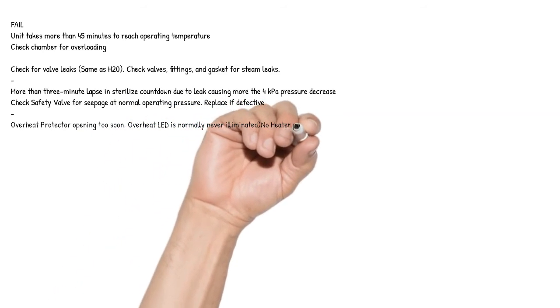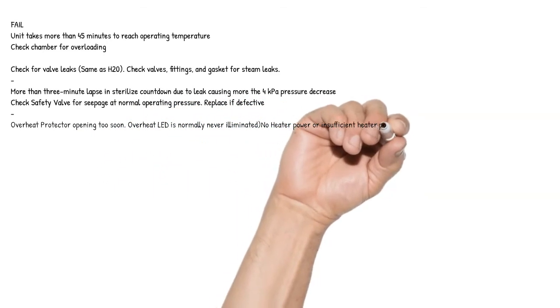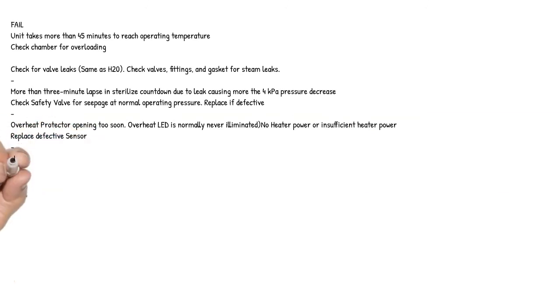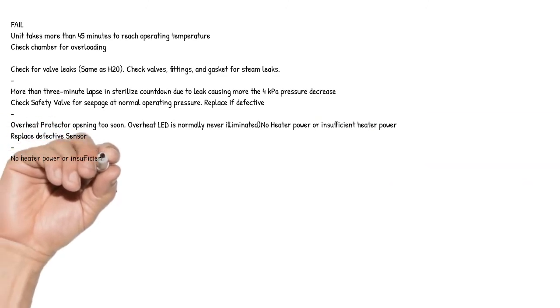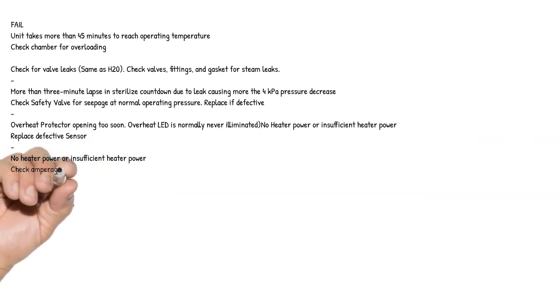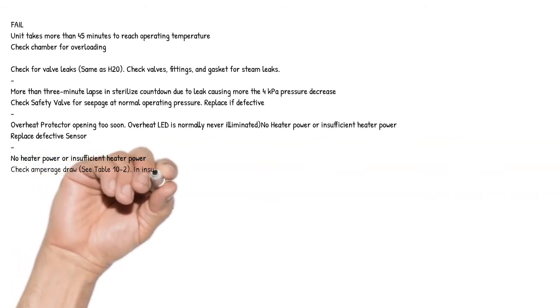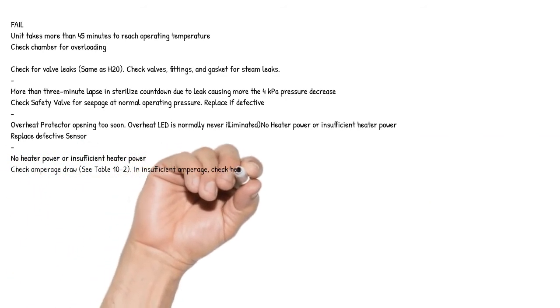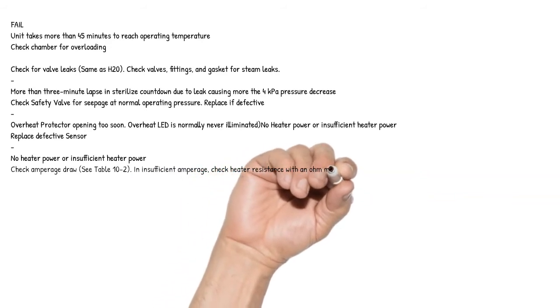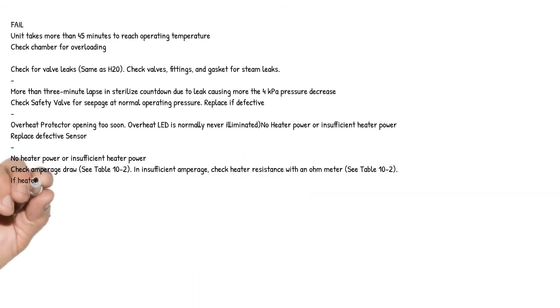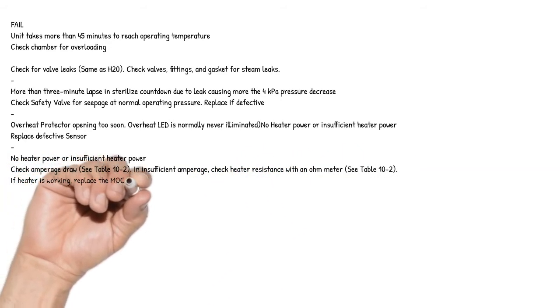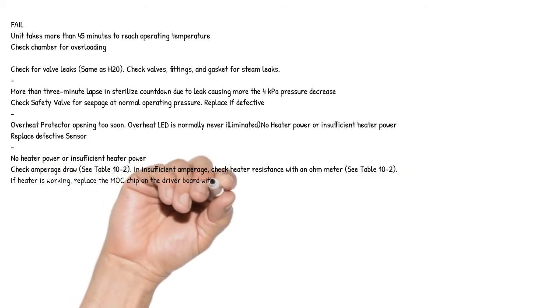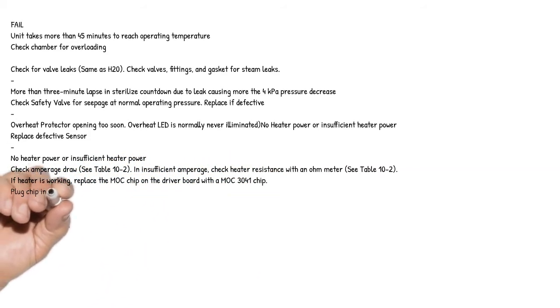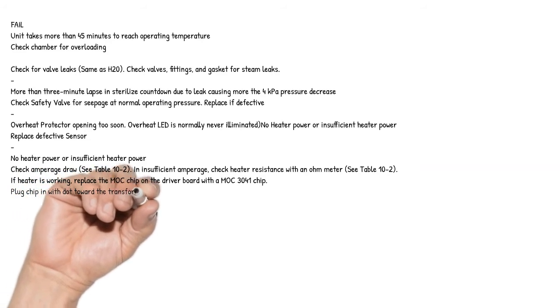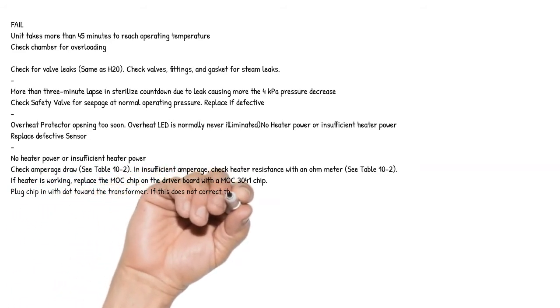No heater power or insufficient heater power. Replace defective sensor. No heater power or insufficient heater power. Check amperage draw, see table 10-2. If insufficient amperage, check heater resistance with an ohm meter, see table 10-2. If heater is working, replace the MOC chip on the driver board with a MOC 3041 chip. Plug chip in with dot toward the transformer. If this does not correct the problem, replace the driver board.